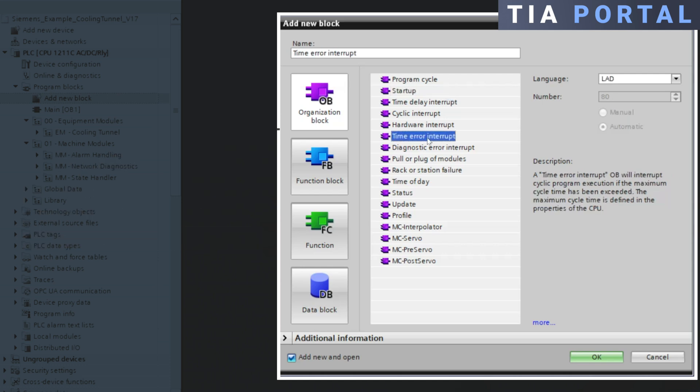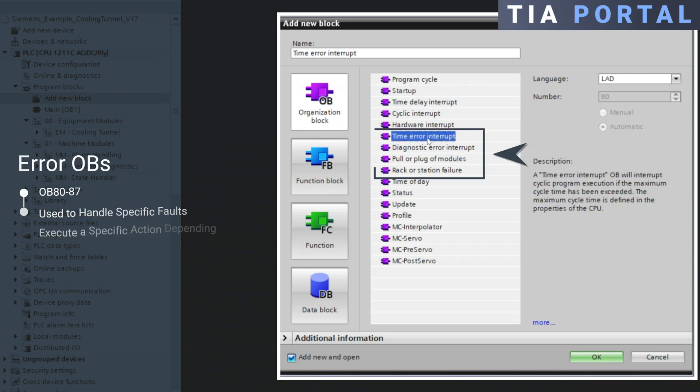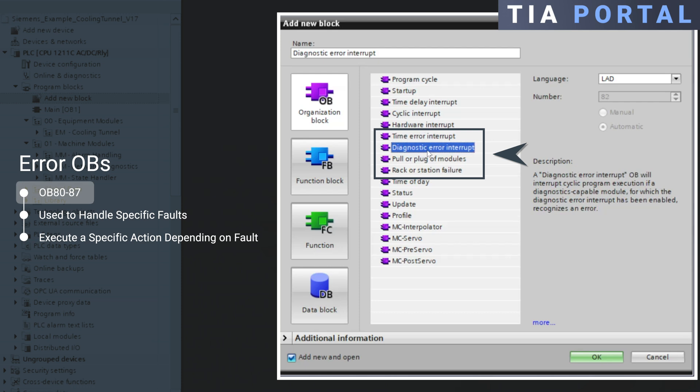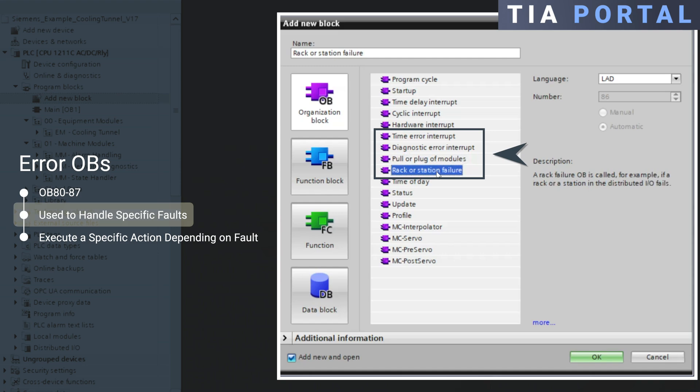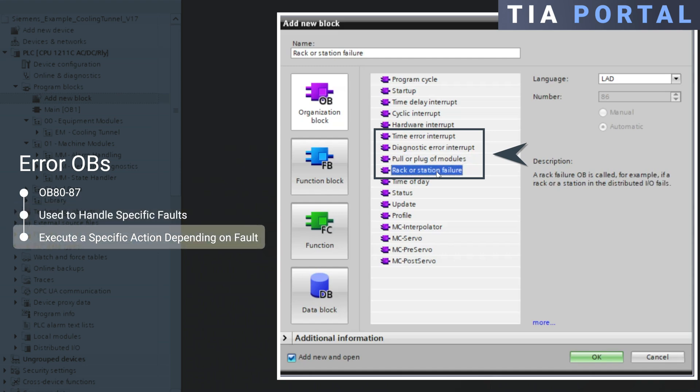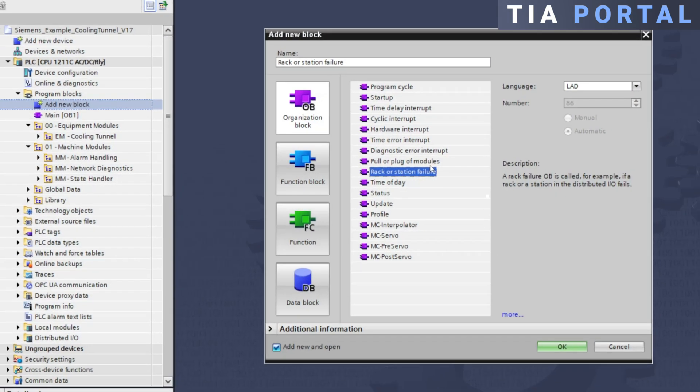And finally, error OBs, ranging from OB80 to OB87, are used to handle specific faults, such as cycle time overlaps, hardware errors, or I-O communication problems. These OBs allow you to execute specific actions in response to various fault scenarios.